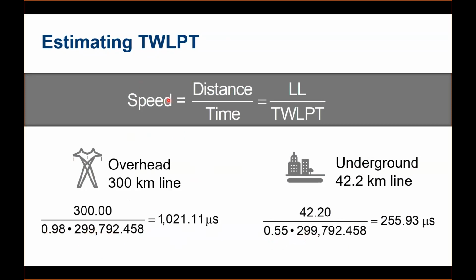So we know the speed, and we know the distance, that is our line length, maybe 300 kilometers in the case of an overhead line. Then we can find the time taken by a traveling wave to travel from one end to the other. This is a constant that we can estimate in microseconds, like about 1021 microseconds for the traveling wave to travel from station S to station R. Similarly, if we have an underground cable of length 42.2 kilometers, the time taken by the traveling wave, or TWLPT, is 255 microseconds. So this is a way to estimate it.